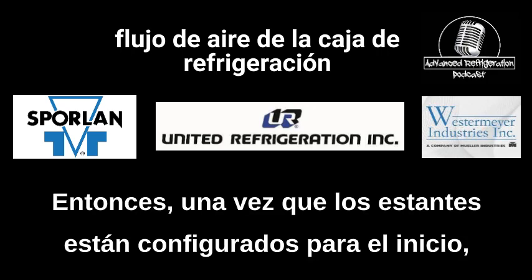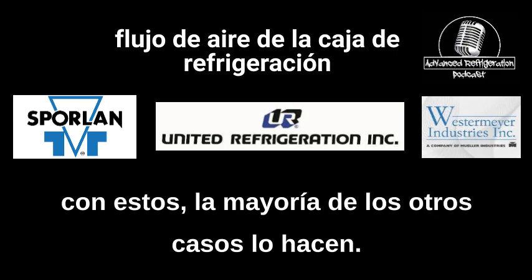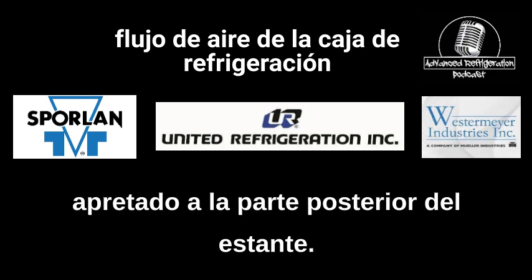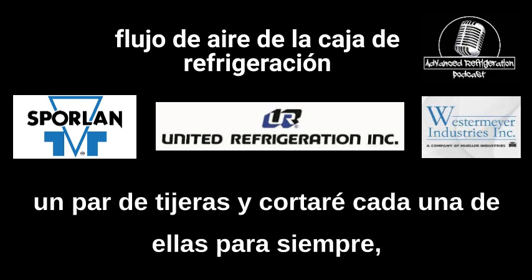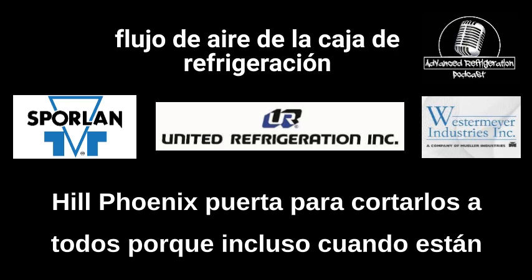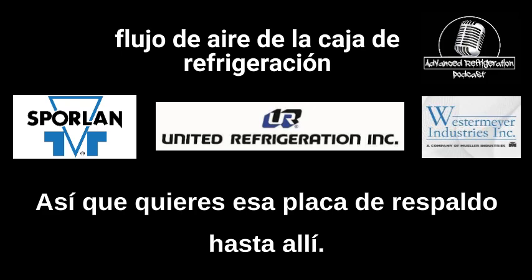So once the shelves are set on startup, because all Hill Phoenix meat cases usually ship like this, most of the other cases do too. On startup they're all zip tied to the back of the shelf, so if you're not paying attention, you'll miss this. On startup, what I'll do is walk around with a pair of scissors and snip every single one. It takes forever. It takes me a good 2-3 hours on a full Hill Phoenix store to cut them all, because even when they're flat, there's still a little bit of a gap. So you want that backing plate all the way on there.